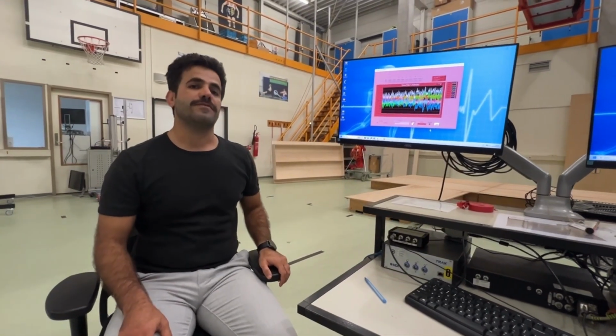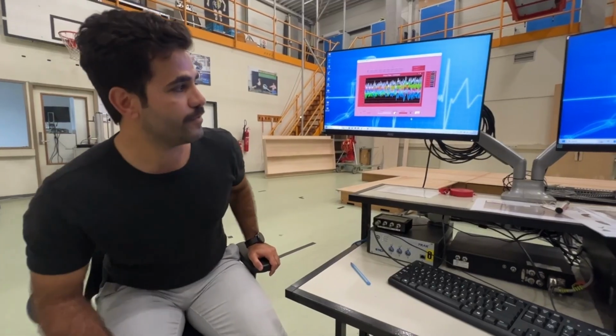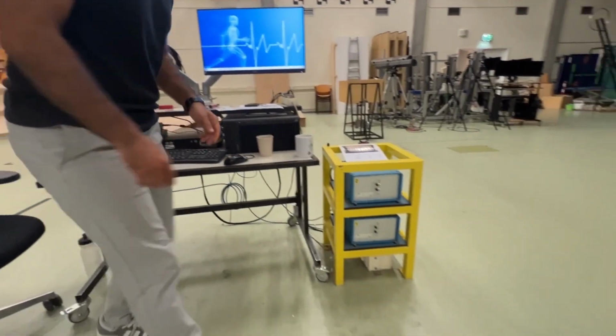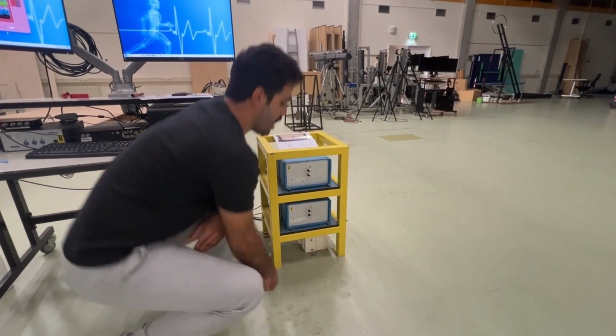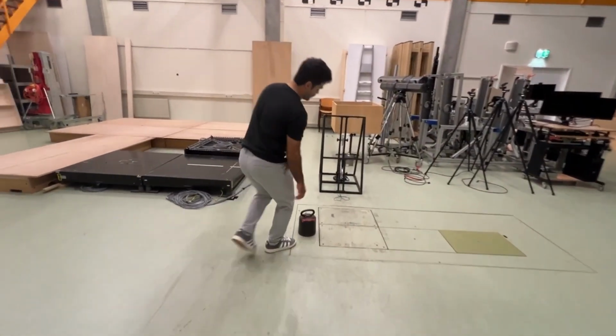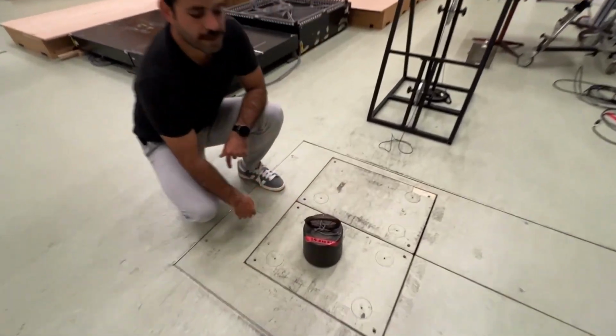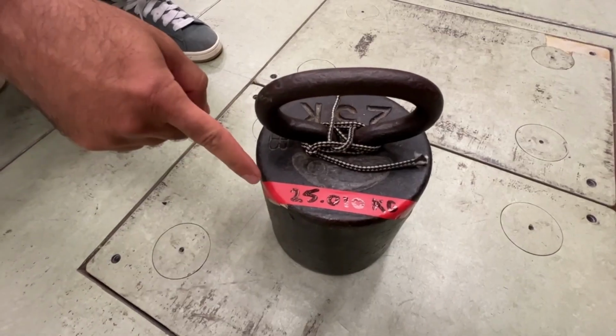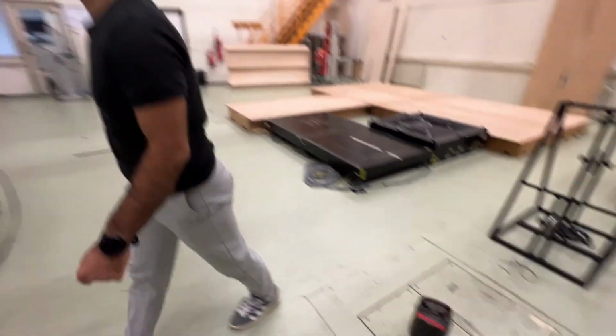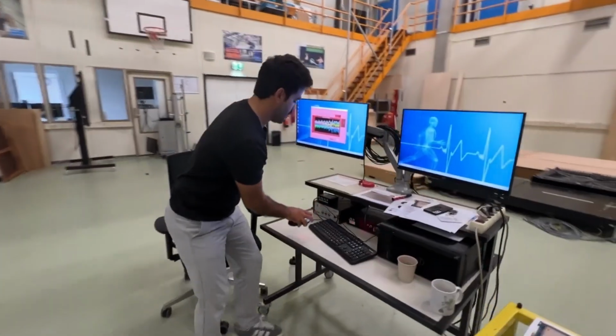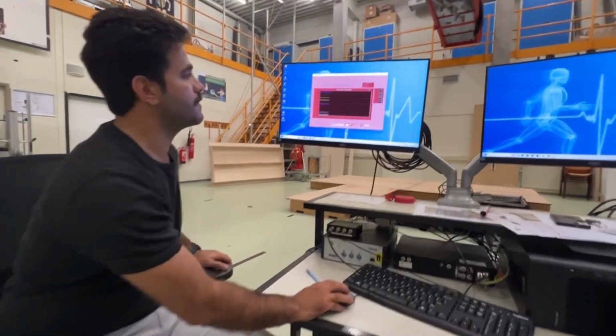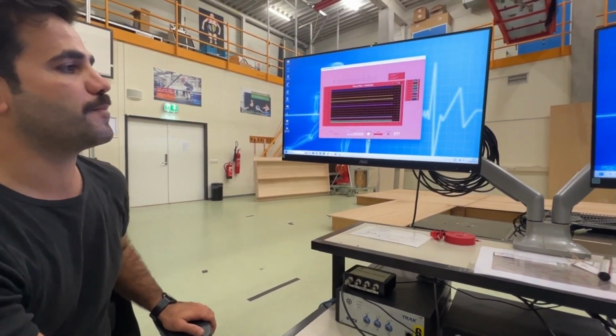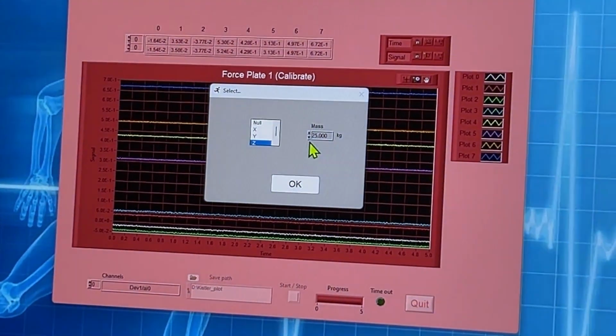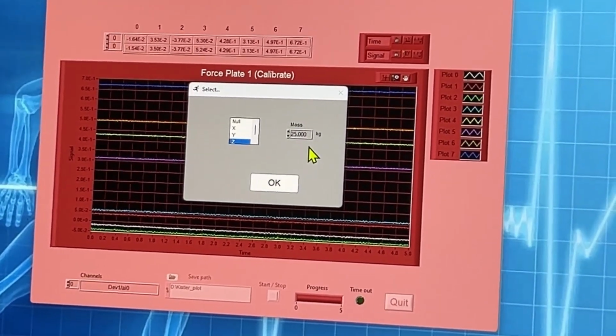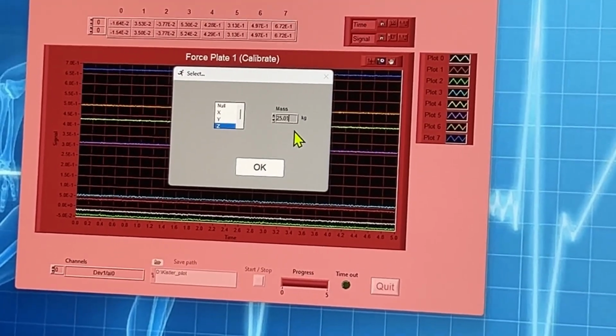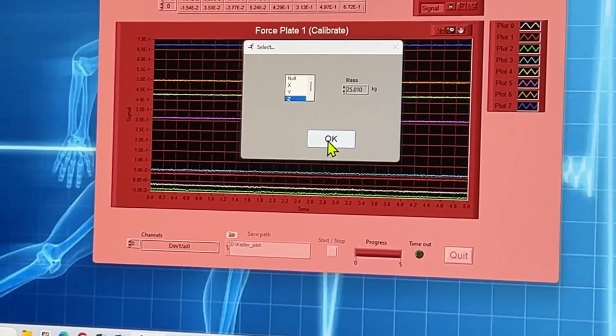Now let's do the calibration of the force plate in vertical or Z direction. For this, we need to do reset of the amplifier first, and we need to put the weight on the force plate. And the exact weight is written on this. So we need to include this number in the system. We click the start button. We choose the Z direction, and we write the exact number of the weight here. And we press OK.